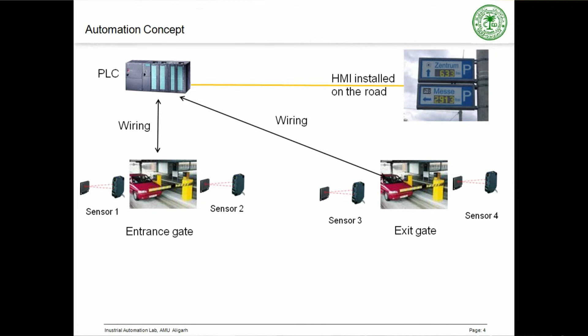Now let us see how actually these are achieved in programming. In this project, we have used the Siemens Total Integrated Automation, that is TIA software, whose PLC is S7300, which is taking the single phase supply, and its CPU is 314C-2 PN/DP, which has multiple interfaces, that is Profinet interface and Profibus interface. In our program, we use only the Profinet interface. Another software used is Siemens WinCC Flexible with touch panel TP177B.